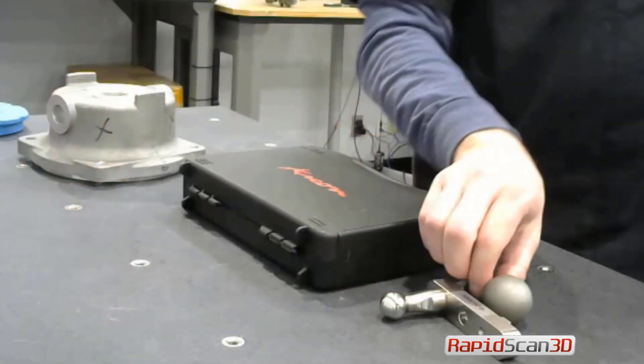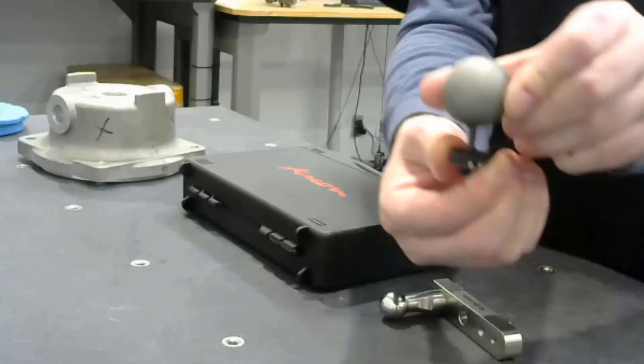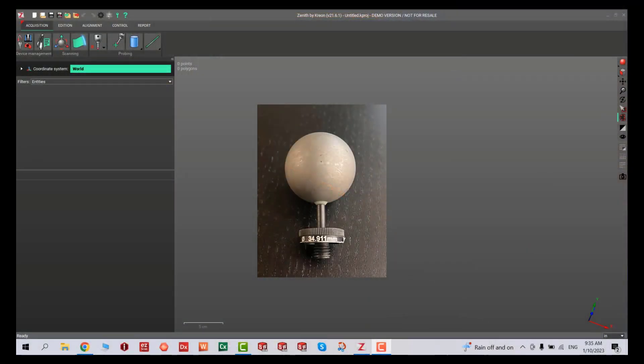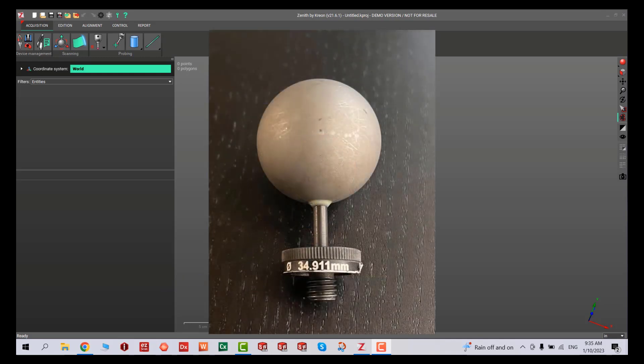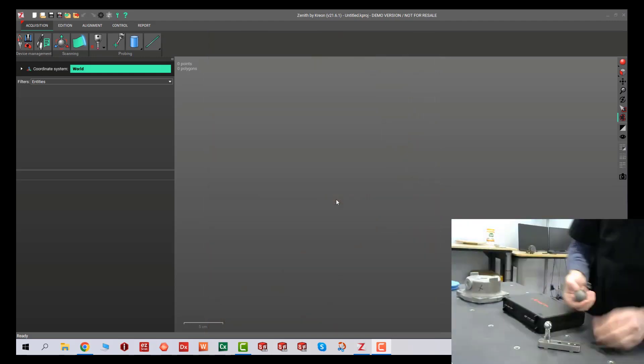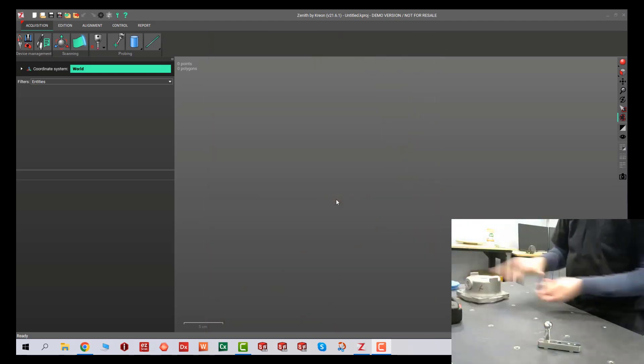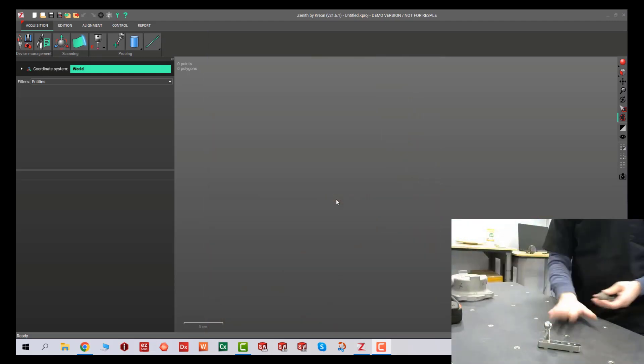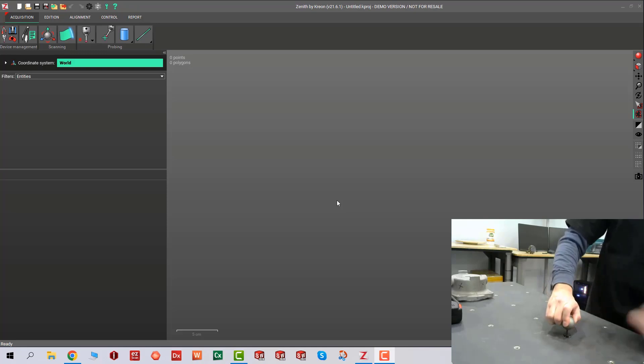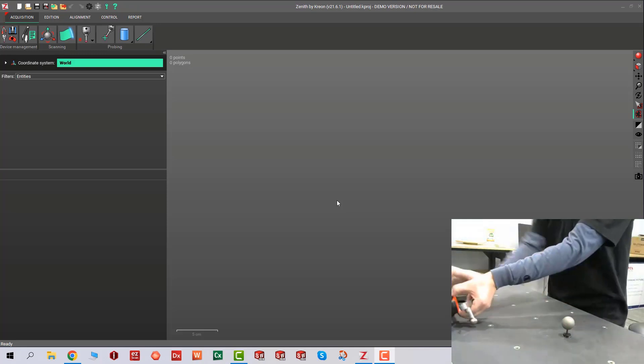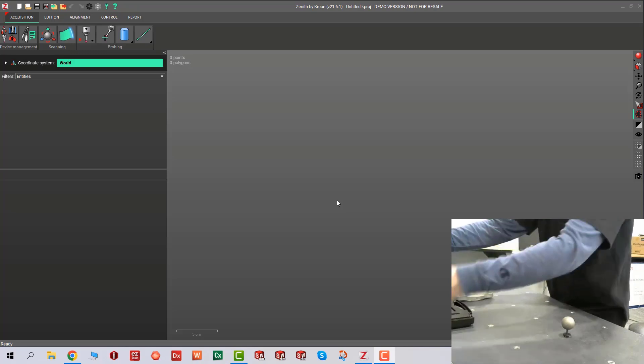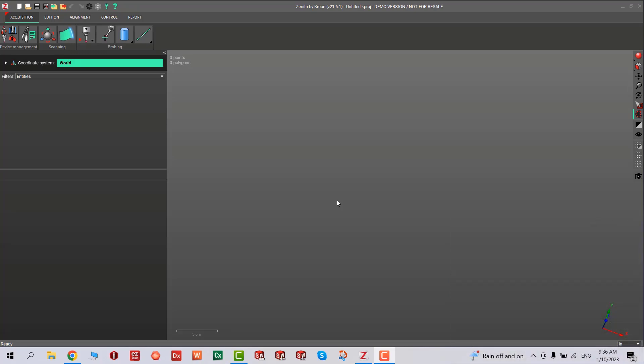First, grab the calibration sphere. There are numbers on it - make sure you write it down: 34.911 millimeters. This will be useful for our calibration. I'm going to screw this onto the inspection table and put the probe away. Be very careful not to damage these components.